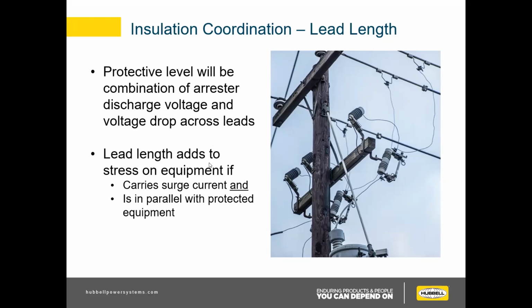So it gets even more hairy here. Not all leads add to the discharge voltage, only leads that are in parallel with the protected equipment and carry surge current. In this case, you have a line lead from the arrestor to the cutout. That is included in your lead length, and then your ground, the distance to the common ground, so that would be to the grounding on the transformer can. Your line from the conductor to the cutout is not in parallel with the protected equipment, so that does not count towards your discharge voltage adder.